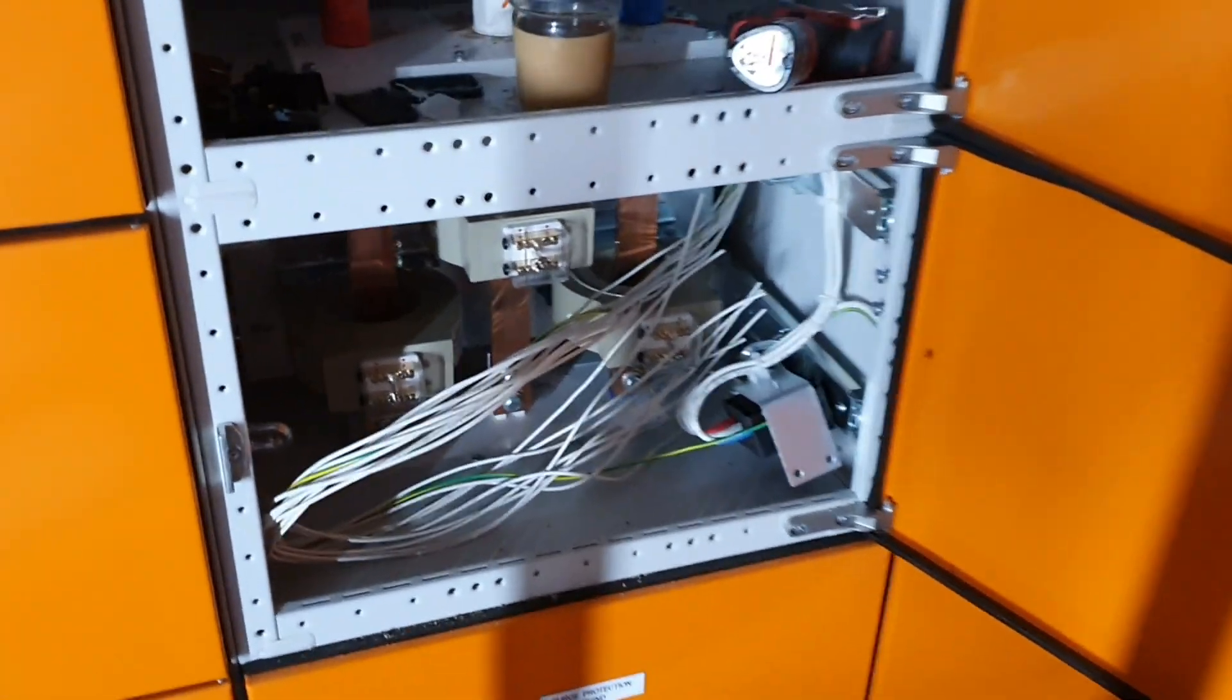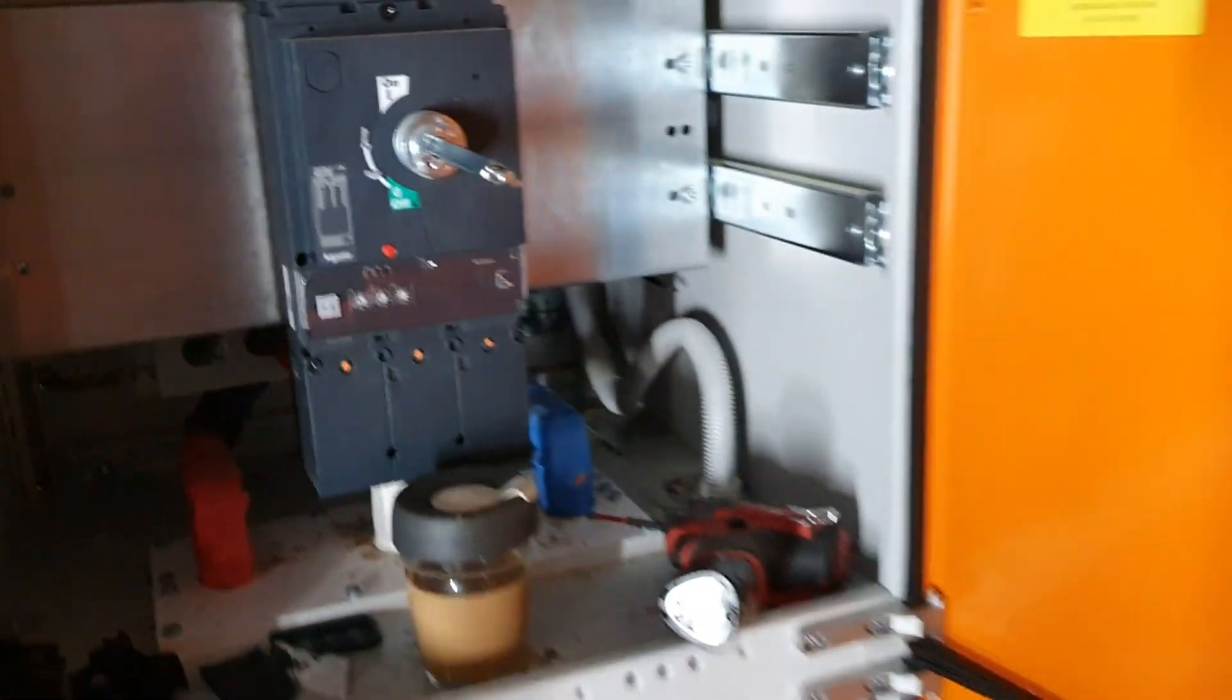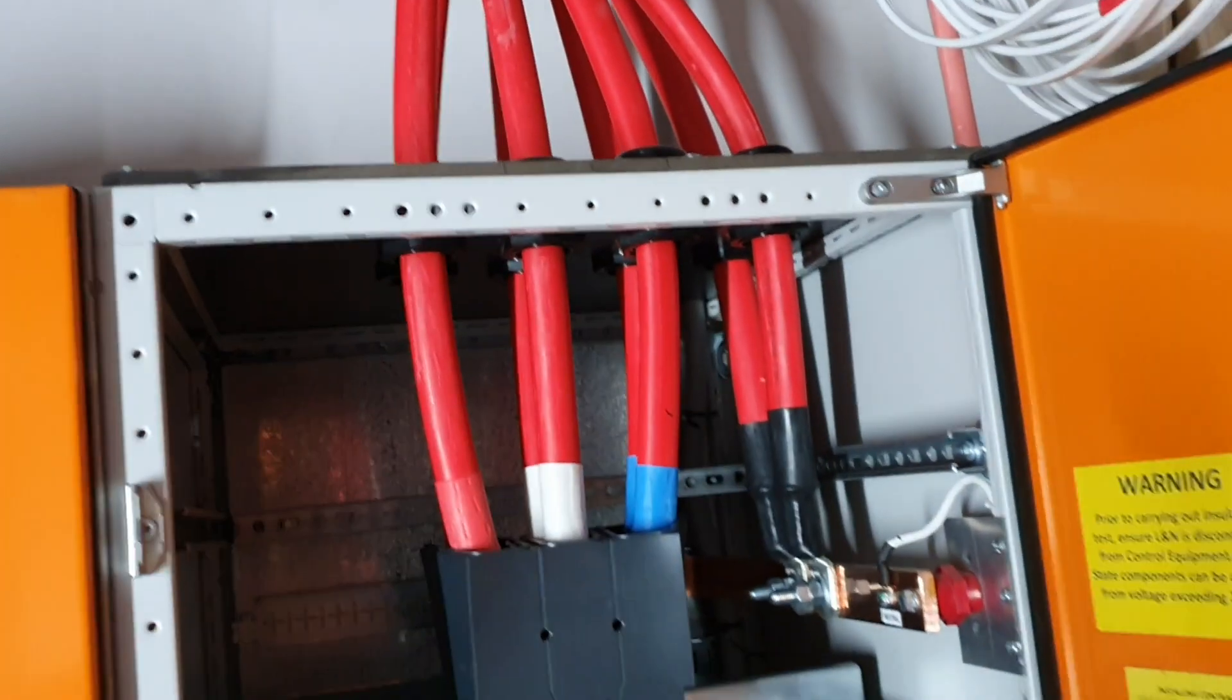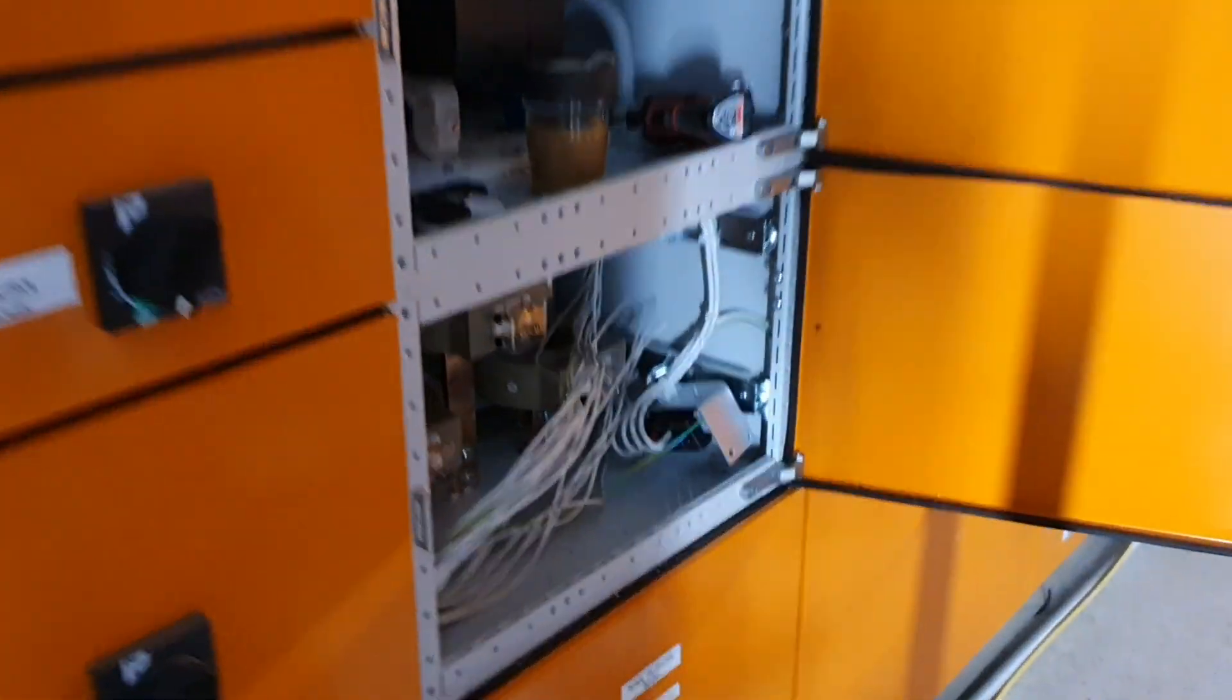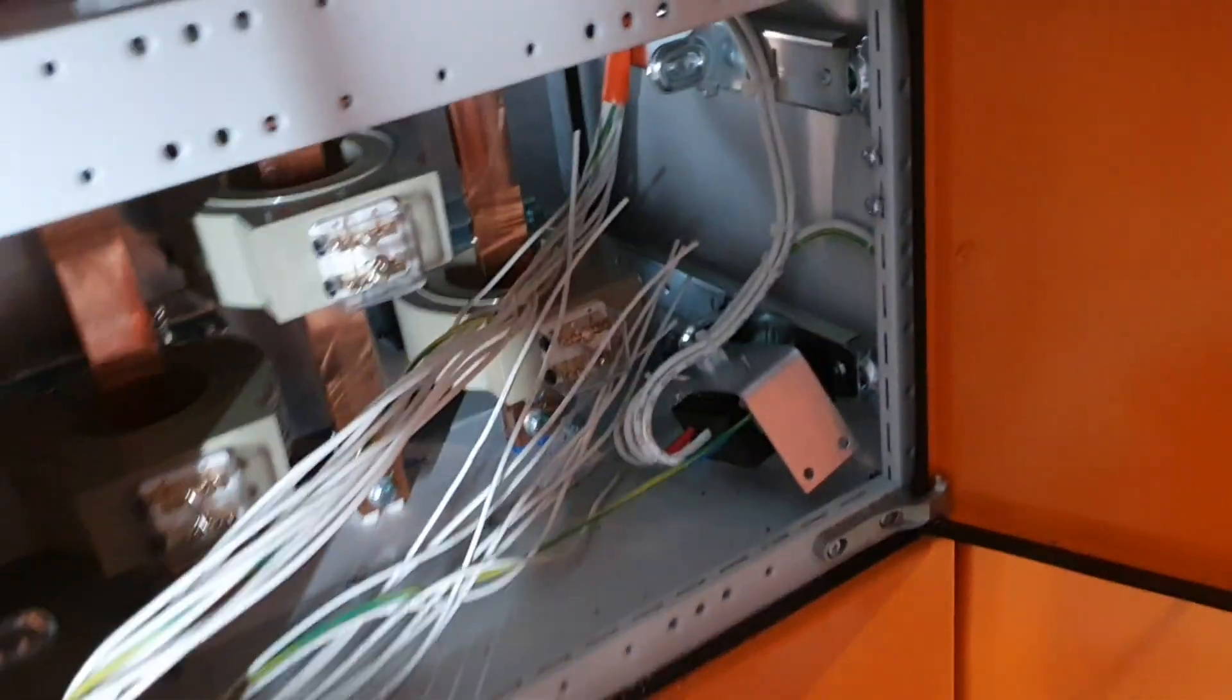Alright, a bit of a bodge job effort I'm not gonna lie. I've got my cable in. So it goes up in the back of the consumer main section, consumer units on the brain. And it comes up across, it's tucked in behind that well into the meter panel. And so we'll have to strip this back and terminate it into the CTs and into that little block that's hanging off because I couldn't get the CT cover out.